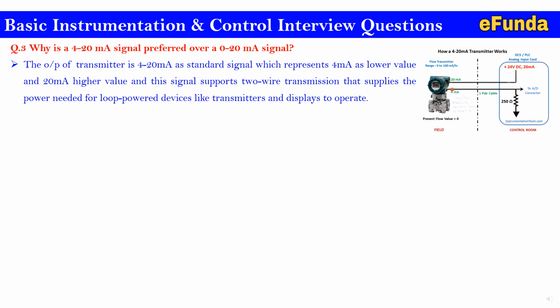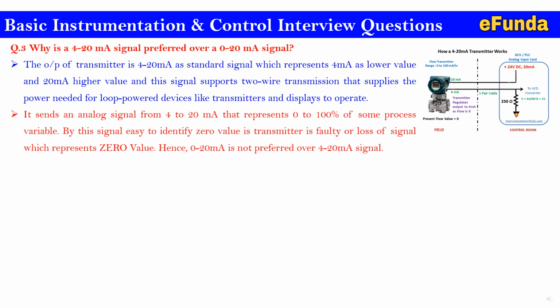instrumentationtools.com, where they have shown an animation of how the current flows from the controller or control system to the transmitter, and from the transmitter the return signal is connected by the pair cable to the control system with the help of an A to D converter and a 250 ohm resistance. It sends an analog signal from 4 to 20 milliamp that represents 0 to 100% of some process variable.